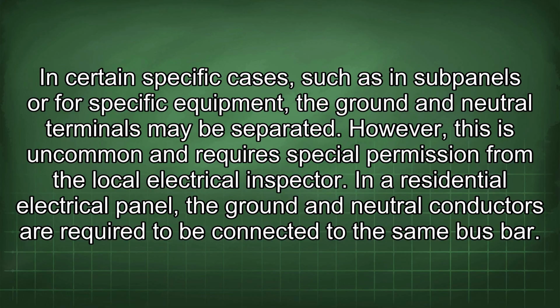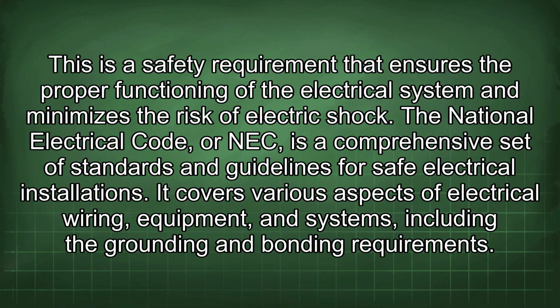In a residential electrical panel, the ground and neutral conductors are required to be connected to the same bus bar. This is a safety requirement that ensures the proper functioning of the electrical system and minimizes the risk of electric shock. The National Electrical Code, or NEC, is a comprehensive set of standards and guidelines for safe electrical installations. It covers various aspects of electrical wiring, equipment, and systems, including the grounding and bonding requirements.